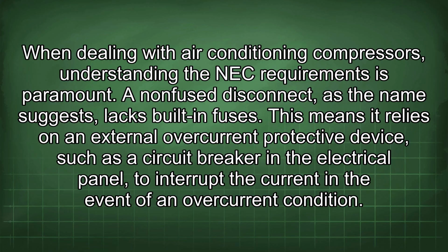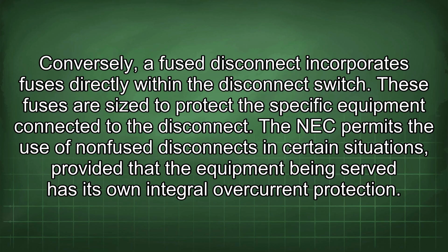A non-fused disconnect, as the name suggests, lacks built-in fuses. This means it relies on an external overcurrent protective device, such as a circuit breaker in the electrical panel, to interrupt the current in the event of an overcurrent condition. Conversely, a fused disconnect incorporates fuses directly within the disconnect switch. These fuses are sized to protect the specific equipment connected to the disconnect.